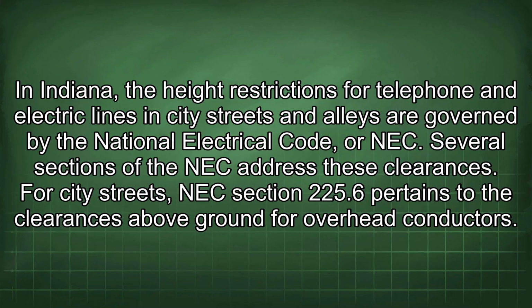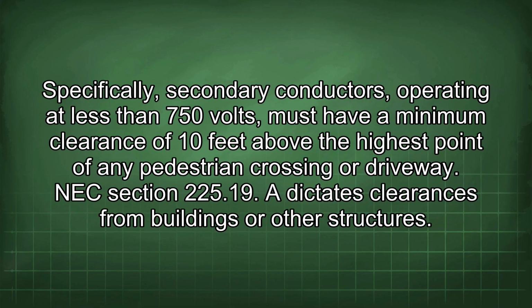In Indiana, the height restrictions for telephone and electric lines in city streets and alleys are governed by the National Electrical Code, or NEC. Several sections of the NEC address these clearances. For city streets, NEC Section 225.6 pertains to the clearances above ground for overhead conductors. Specifically, secondary conductors operating at less than 750 volts must have a minimum clearance of 10 feet above the highest point of any pedestrian crossing or driveway.